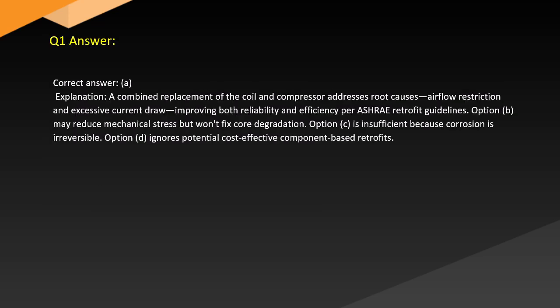Answer. Correct answer: A. Explanation. A combined replacement of the coil and compressor addresses root causes, airflow restriction and excessive current draw, improving both reliability and efficiency per ASHRAE retrofit guidelines.